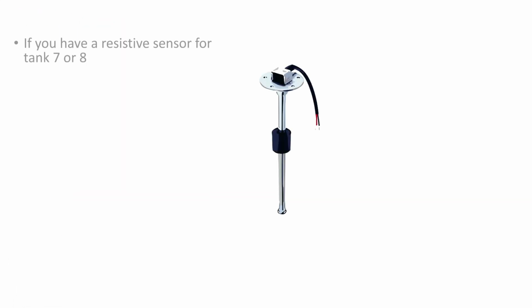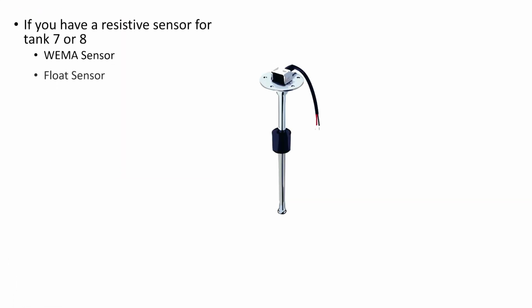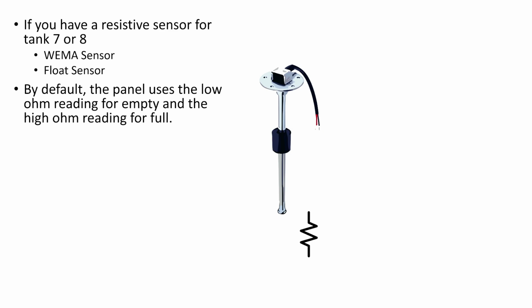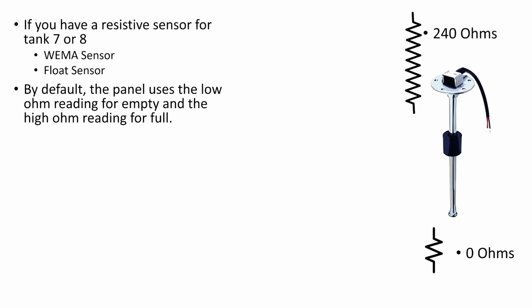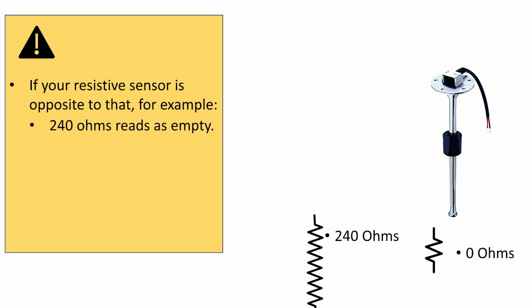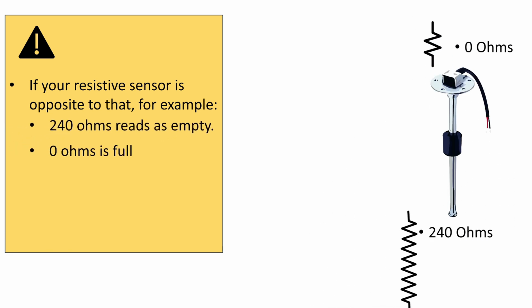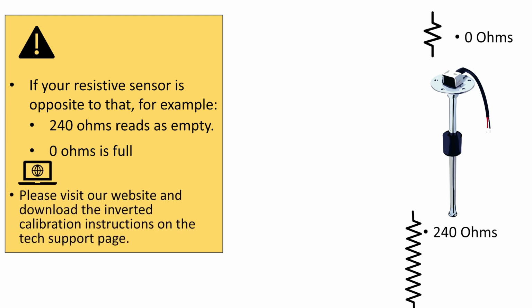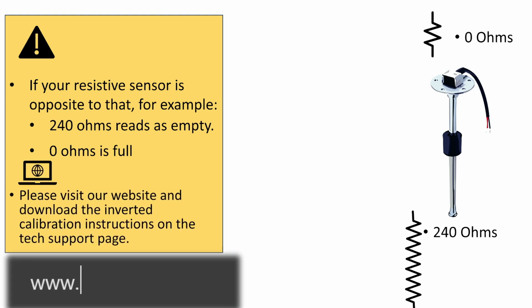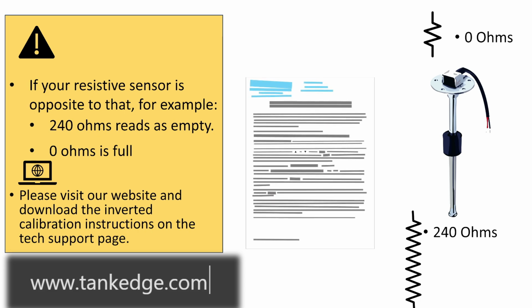The standard program setup for resistive sensors has the low ohm setting for empty and the high ohm setting for full. For example, 0 to 240 ohms, where 0 is empty and 240 is full. Some resistive sensors have that reversed, with the high ohm setting as empty and the low ohm setting as full. If this is the case for your sensor, we have a datasheet on our website at www.tankedge.com. On the tech support page, under resistive sensors, you can find the instructions for an inverted resistive sensor.